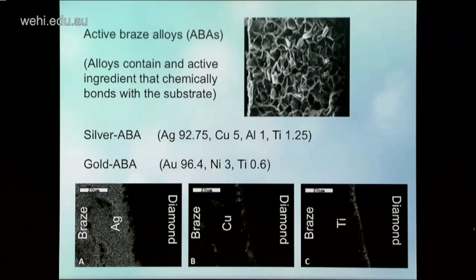So we had to go with a gold-based brazed alloy. This is the makeup of this particular alloy, almost all gold, tiny bit of nickel, and a very, very small amount of titanium. So this, you can make it work through a lot of trickery, but it's just nowhere near as friendly to use. However, it turned out to be quite biocompatible, so we did back muscle implants in guinea pigs with this for 6 months and got a similar sort of immunohistological response to medical grade silicone. So that was our go-to guy, really, gold ABA.